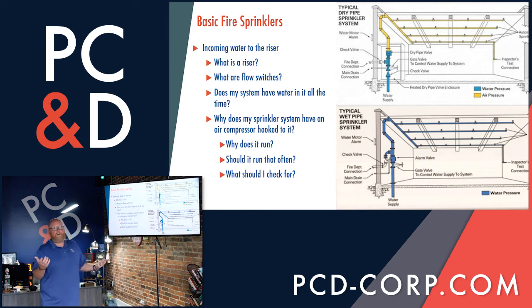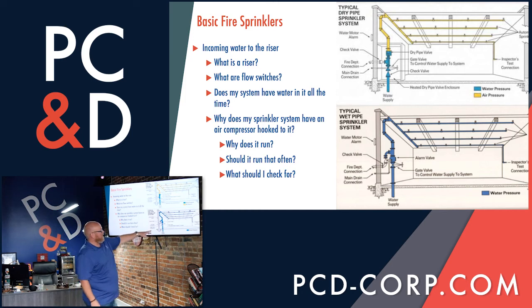Wet is probably what you would think it is. The system's always charged with water. It literally has water at every sprinkler head. It's ready to go. So if you look at this diagram, the blue piping that we have here is what you'll have throughout your building, and your heads are placed every so often to have the appropriate coverage. Everything you see in blue here is wet, from the water coming in up through what's known as your riser. In your sprinkler rooms in your building somewhere, you have what's called the sprinkler riser.